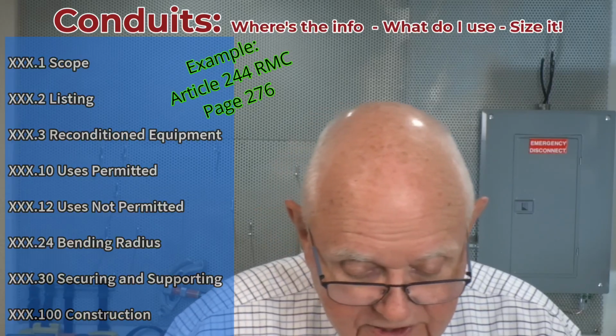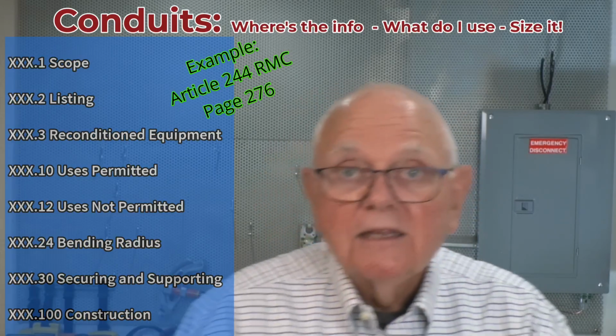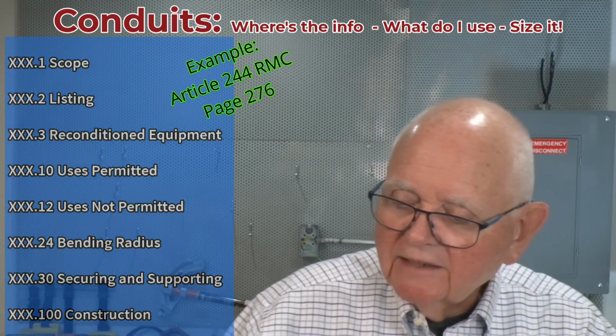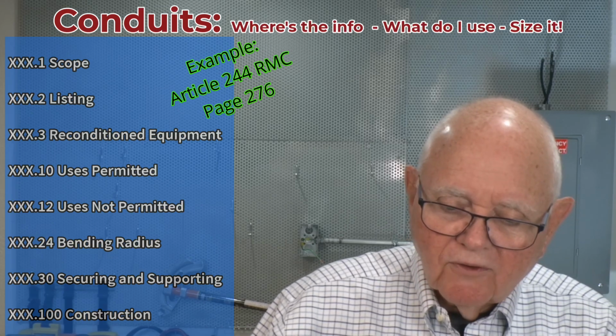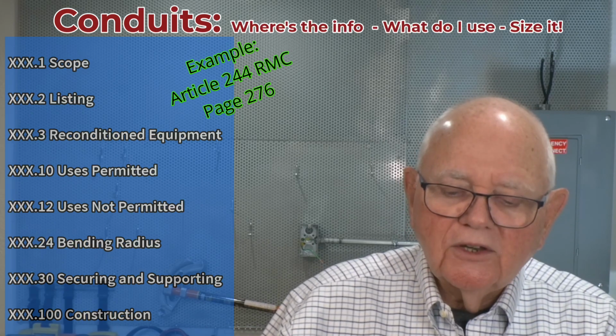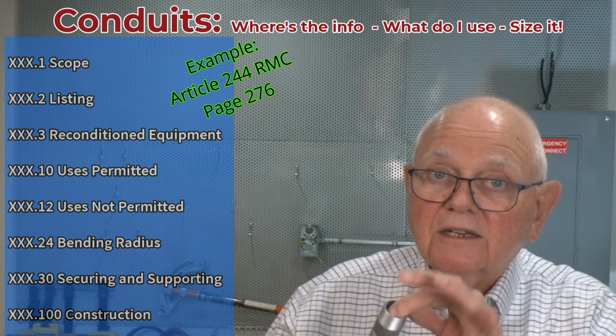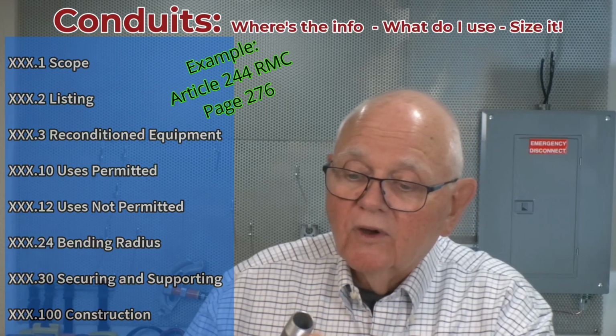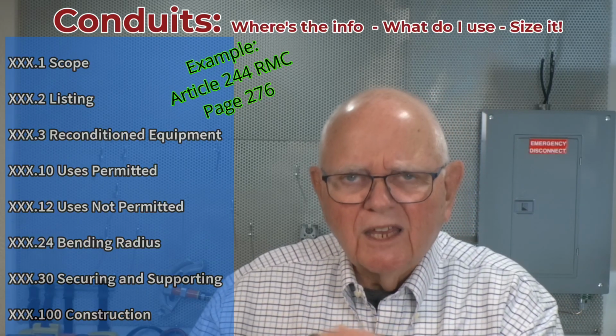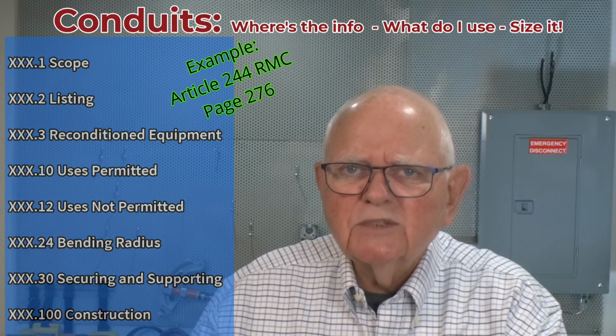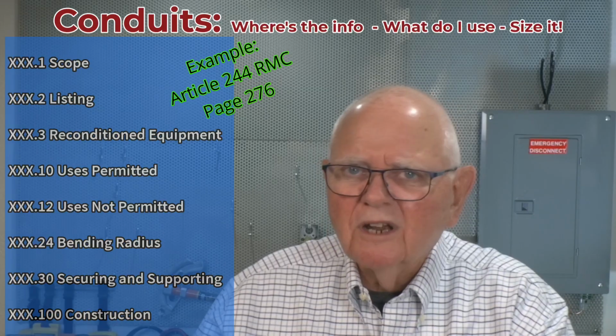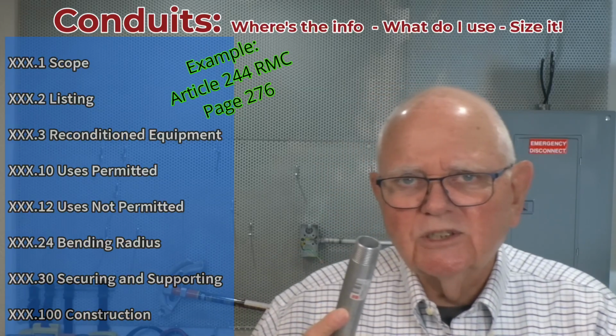Reaming and threading is dot 28. Yeah, so rigid conduit, after I go ahead and I cut and I thread my rigid conduit, it's going to be really sharp right in here, isn't it? So I'm going to have to go ahead and ream that out, and it flares it out is what it does, smooths it out. If not, I pull conductors across there, I could damage some insulation.